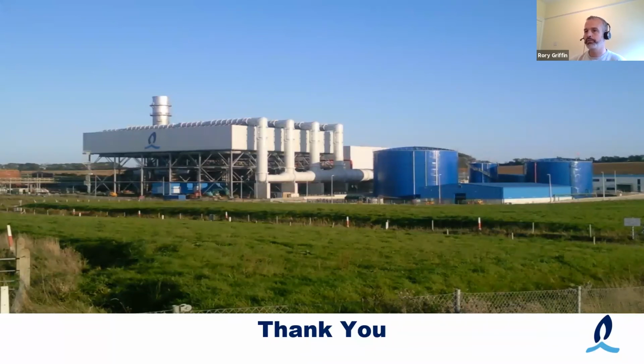Thankfully, the ESB site down the road is a very strategic site. It's one of the black start stations of Ireland. On that site, they have diesel generators that can start an open cycle gas turbine. They could maybe synchronize a second one. There is black start at the Lee station, just west of Cork City. So historically, they'd try and bring a supply from Lee to the Marina station in Cork City, bring a supply up from Aghada. They'd synchronize the two stations there. And once they start building stability, then they might start considering bringing on something like Whitegate.